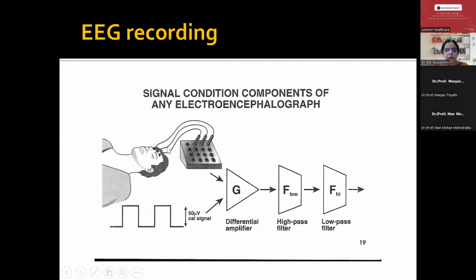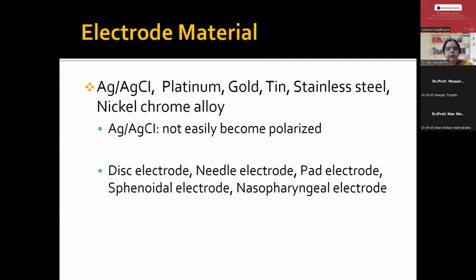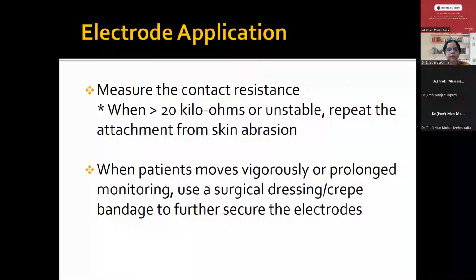So this is just to summarize the EEG system, which goes to the junction box. And after that, the amplifier contains something called a differential amplifier, after which the EEG signal goes through a low frequency filter and a high frequency filter. So we'll come to the details of this. So all this one should be aware of. And the electrodes are usually made up of silver chloride, which usually are not polarized. So we can use a disc electrode, needle electrode, pad electrode. Most of the time we are using a cup electrode.